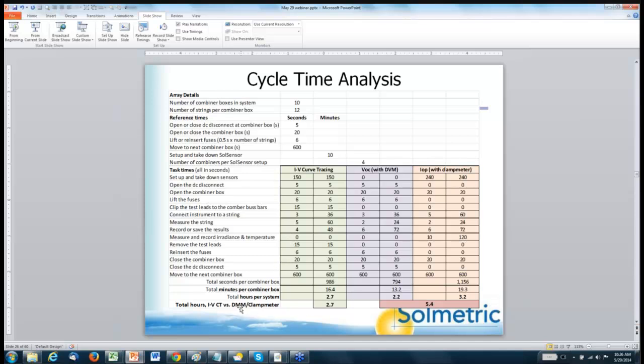For the various assumptions I made, the total hours for the system for IV curve tracing was 2.7 hours. And the total time for doing it with discrete measurements was 2.2 plus 3.2, or 5.4 hours. So roughly a 2-to-1 difference.